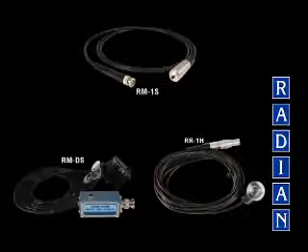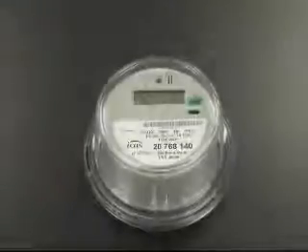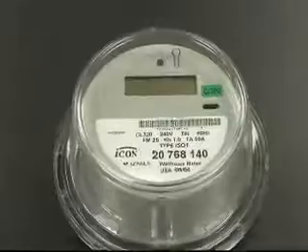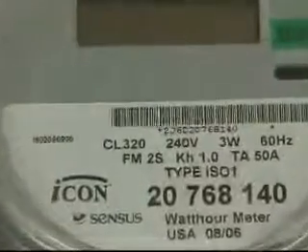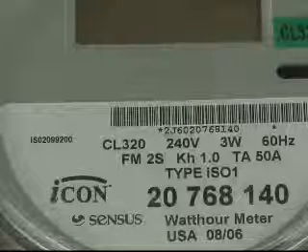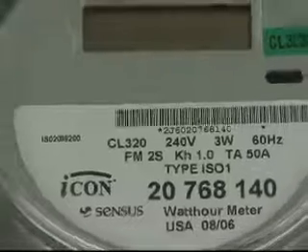Make all appropriate current and potential connections between the meter and the phantom load. At this time, note the information located on the meter's faceplate. This information should include the meter's K sub H, test amperage, service voltage, and current class. Also connect the pulse pickup sensor.